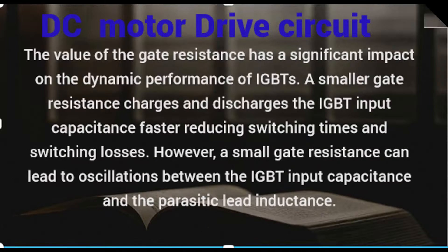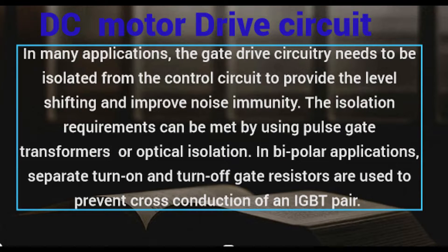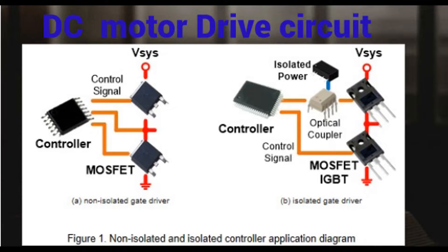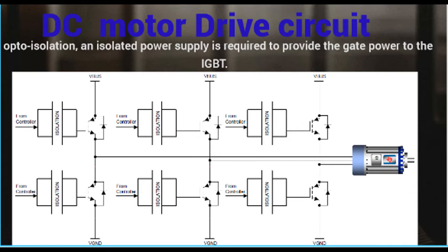The value of the gate resistance has a significant impact on the dynamic performance of IGBTs. A smaller gate resistance charges and discharges the IGBT input capacitance faster, reducing switching times and switching losses. However, a small gate resistance can lead to oscillations between the IGBT input capacitance and the parasitic lead inductance. Within many applications, the gate-drive circuitry needs to be isolated from the control circuit to provide level-shifting and improve noise immunity. The isolation requirements can be met by using pulse-gate transformers or optical isolation. In bipolar applications, separate turn-on and turn-off gate resistors are used to prevent cross-conduction of an IGBT pair. Opto-isolation with an isolated power supply is required to provide the gate power to the IGBT.